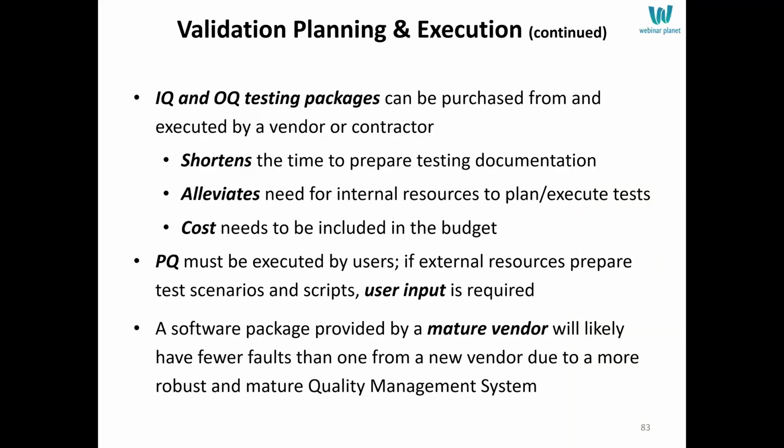Now you can purchase an IQ, OQ test package from many vendors. They sell these. They'll also sell you the service to actually execute IQ and OQ. And this is perfectly acceptable. However, you must make sure you audit the vendor or the contractor, you vet them, make sure that they are capable of doing this work properly. And then you still have to have oversight to everything they do. You must review and approve all of their work. Review and approve their plans before they execute those protocols, and then review and approve the work that they collect. So this can be a big time savings, but it comes at a cost.